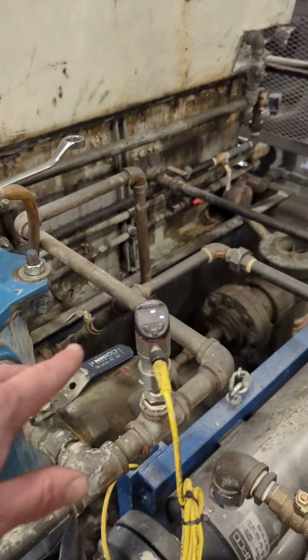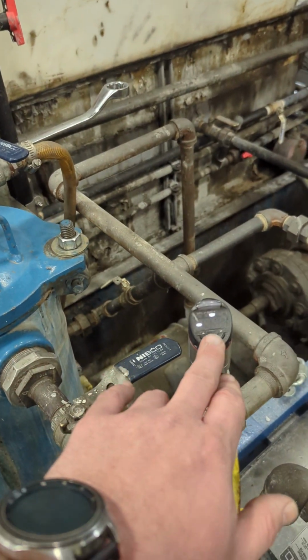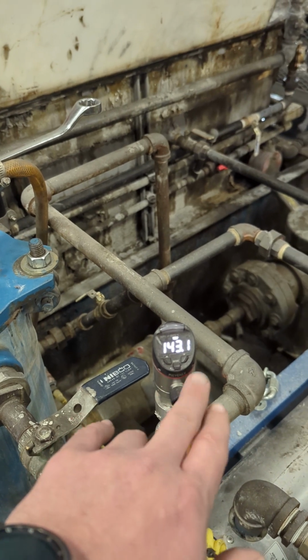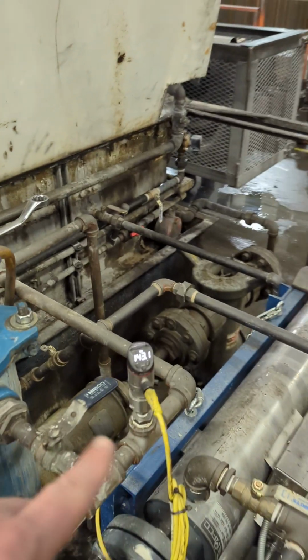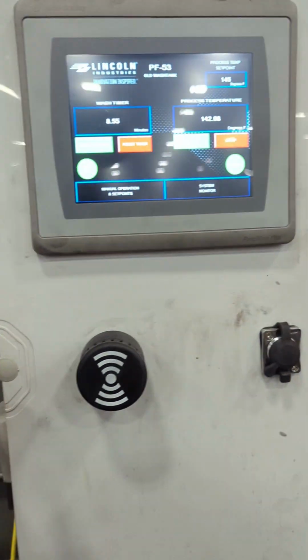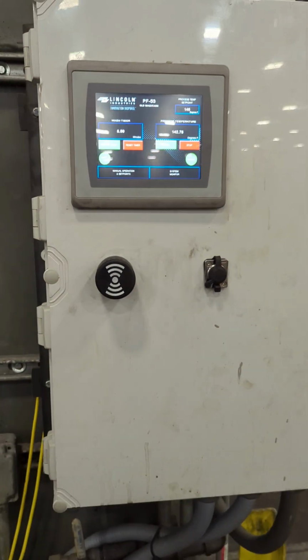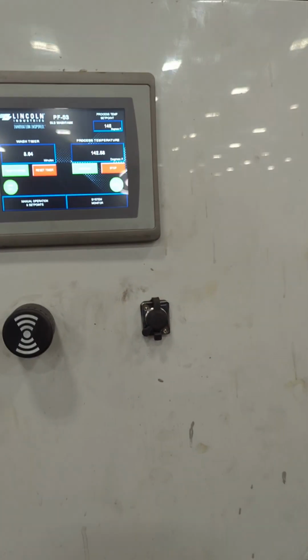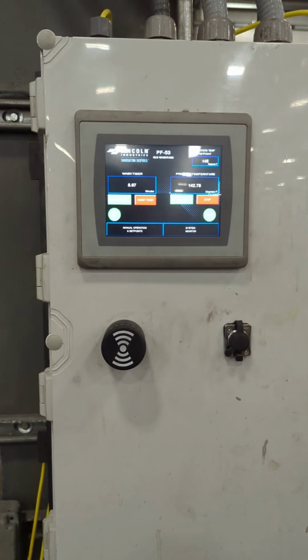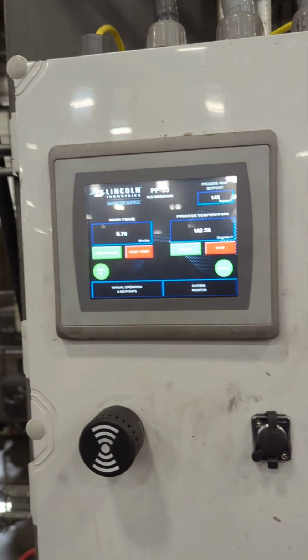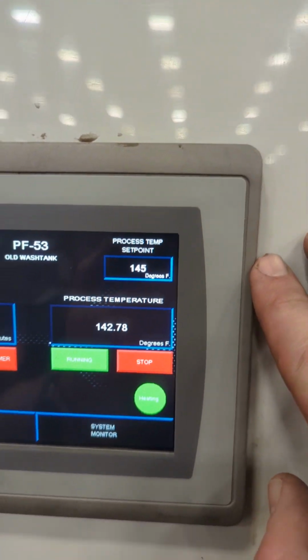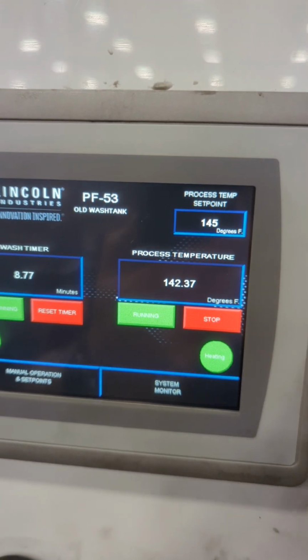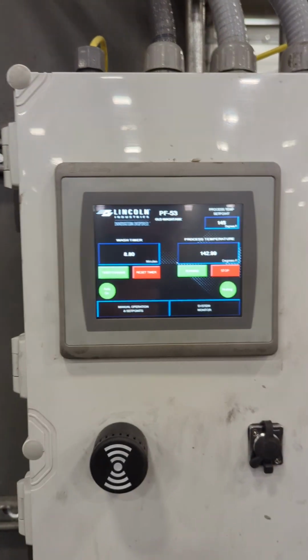We use this Keyence sensor. It's a transducer, pressure and temperature. It gives me a 4 to 20 milliamp signal that I ran into the box in here. I actually put that into a signal conditioner. Got 4 to 20 milliamp, 0 to 5 volts, and then scaled it down from there. And then there's my process temperature from that point right there.